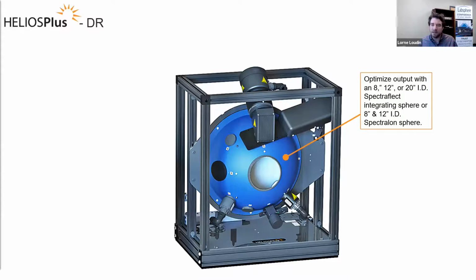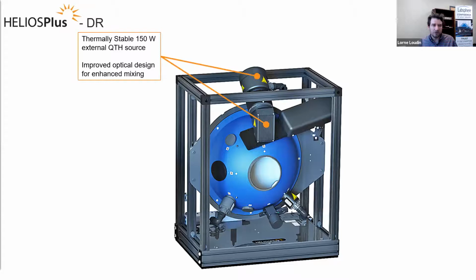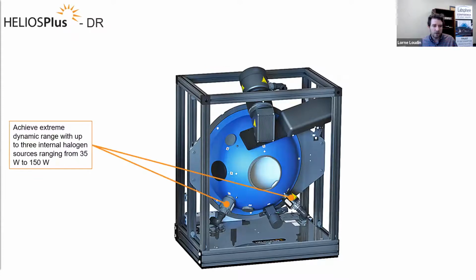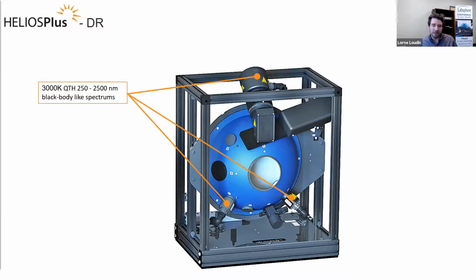So here you can see we've added an additional sphere size in the 8-inch in both our SpectraFlect and Spectralon models. So you can choose from an 8 to 20-inch sphere or 8 to 12-inch in Spectralon. You have the same thermally stable 150-watt source as you have on the A family. Note here that you have 2 options for internal halogen sources, ranging from 35 watt to 150 watt. And again, the combined effect of these is a 3000K QTH black body like spectrum.